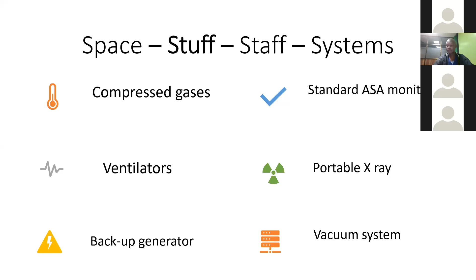Most ventilators operate at a supply pressure of around 50 psi and a flow of about 80 liters per minute. Excessive pressures will damage the safety valves, and there will be excessive leak and malfunctioning of the ventilators. A power conditioner should be used to deliver electricity to all devices and machines. Remember to have a backup generator. Telecommunication will involve telephone, intercom, manually triggered alarms, large wall clock and calendars, computer, and internet. Essential to have reliable supply chain and PPM arrangement, as PPM stands for Planned Preventive Maintenance.